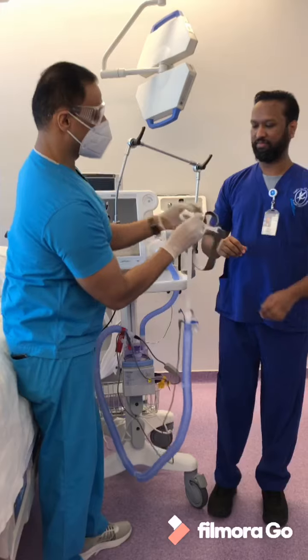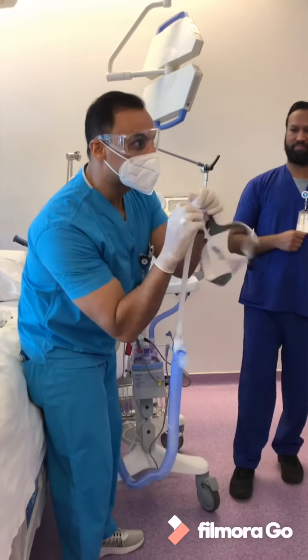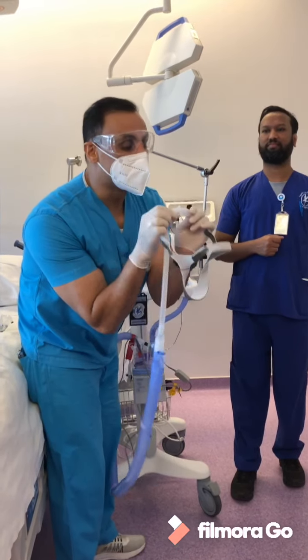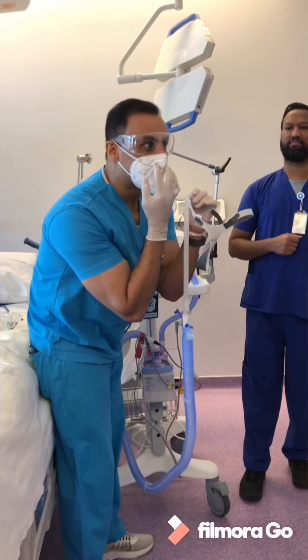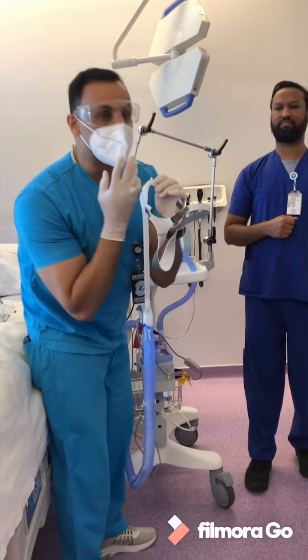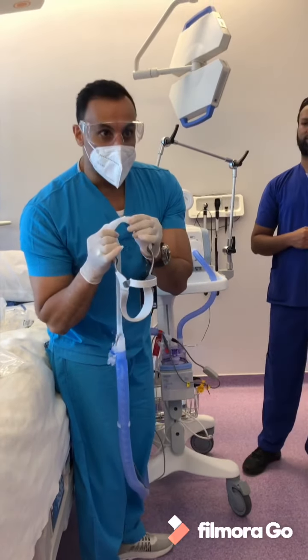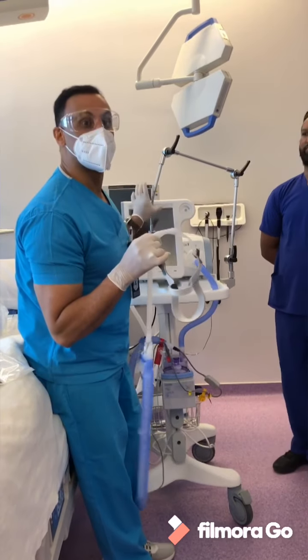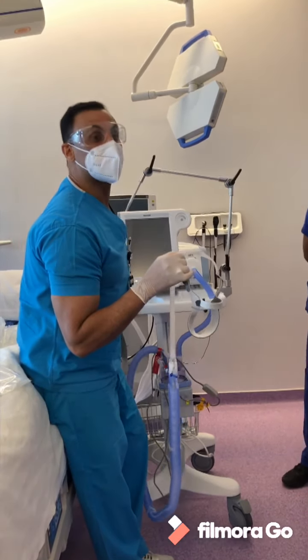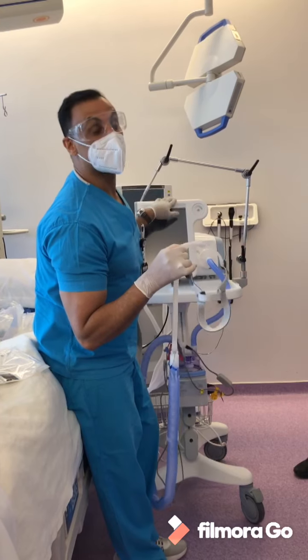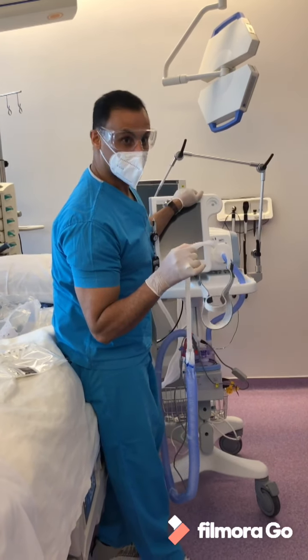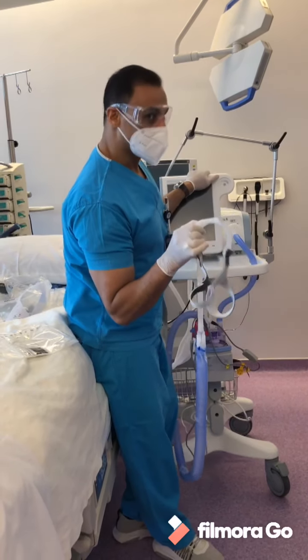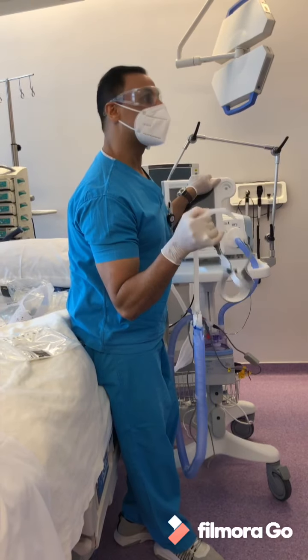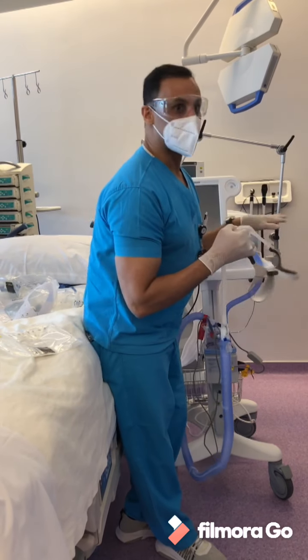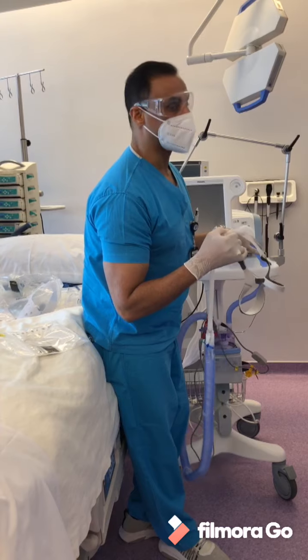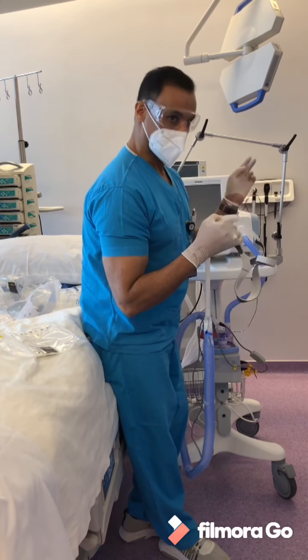So this one goes in, not out. If it's out, it will touch the mucosa, and then it will block the flow. And then here you will have an alarm that says blockage or not reaching the recommended flow. Okay, so that's the troubleshooting of this machine. We already said it. Not many alarms on this one. You have only 2 alarms. I will talk about it later.